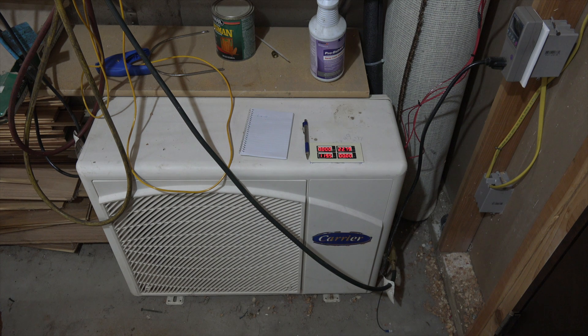To give you an idea of how this is set up — this is actually located inside a building, in a basement. It's got a very stable temperature throughout the year. The reason I put it here was because I did not want the varying outside air temperatures to affect the readings. This unit has a fan that is pressure controlled — it usually runs without the fan, even up to fairly high ambient temperatures.